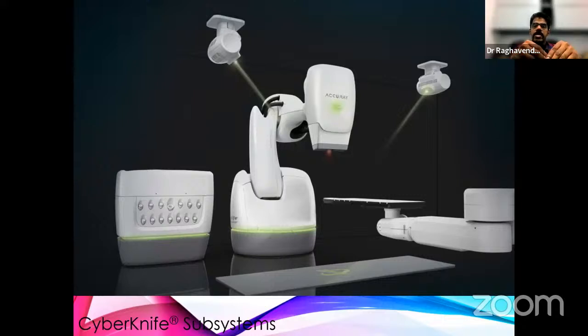If you are looking at non-frame or frameless radiosurgeries, this is the choice, the CyberKnife. Here, this part is the linear accelerator, an X-band LINAC, the high frequency one, compared to the S-band linear accelerators.